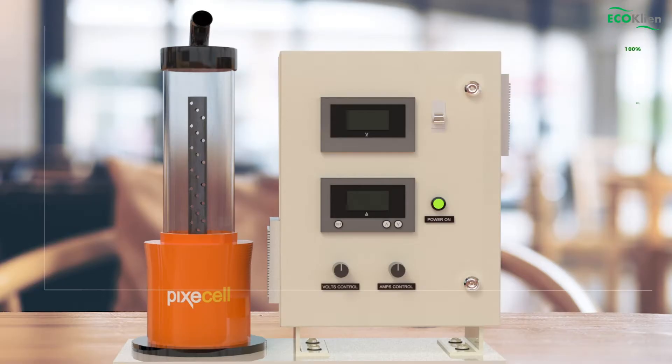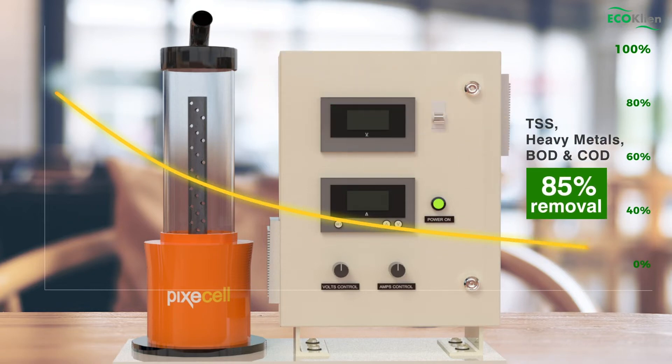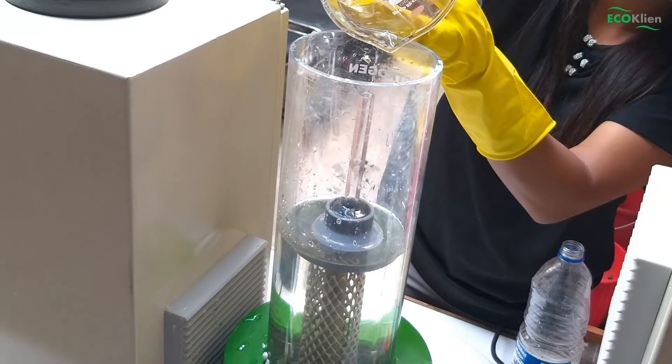Electrolysis of the effluent in the reactor ensures free flow of electrons, destabilizing the surface charges on suspended solids, heavy metals, and organic compounds, forming large flocs that finally settle down, providing a clear liquid with 60 to 85 percent removal efficiency of TSS, heavy metals, BOD, and COD.